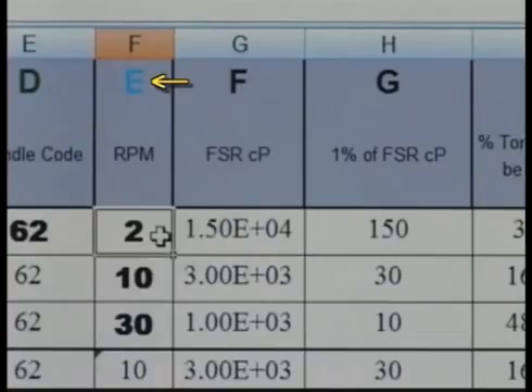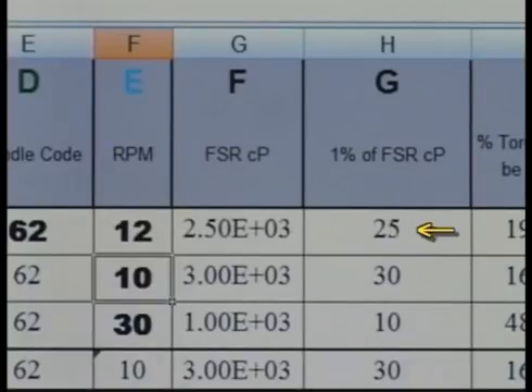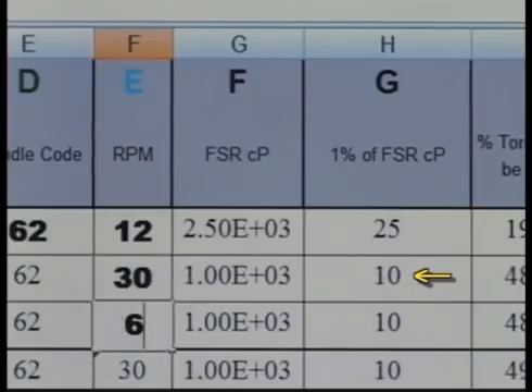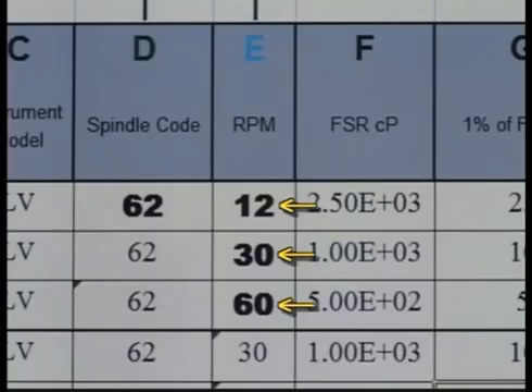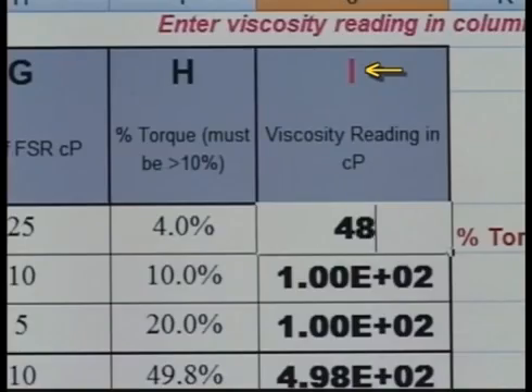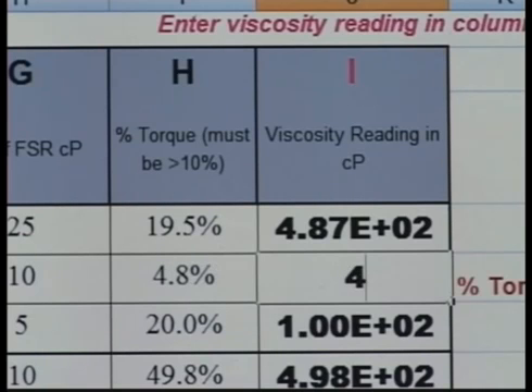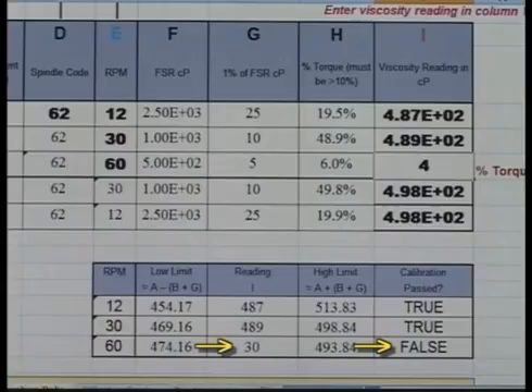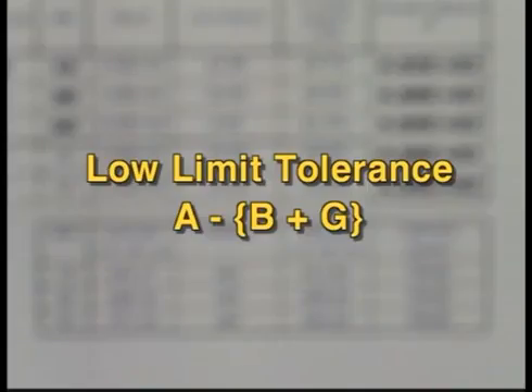Enter the 3 speeds you will be running in column E and observe the 1% full-scale range in column G is updated. This is the accuracy of the viscometer at this range. Now, run the 3 speeds you have selected. Record and enter the data in column I. Your results will show up in the box below. The low limit tolerance is column A, the actual fluid value, minus column B plus G, which is the 1% value of the fluid, plus the 1% value of the full-scale range. The high limit tolerance is merely column A, the actual fluid value, plus column B plus G, which is the 1% value of the fluid, plus the 1% value of the full-scale range.